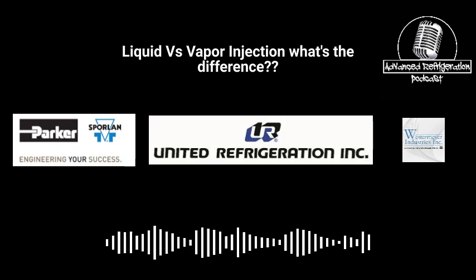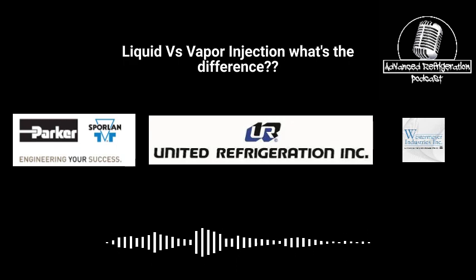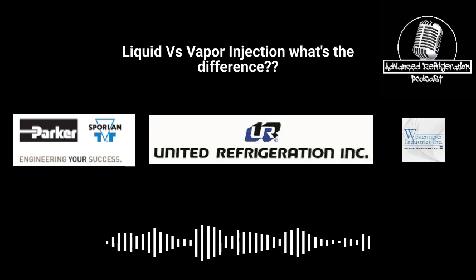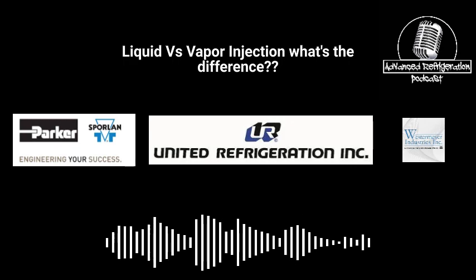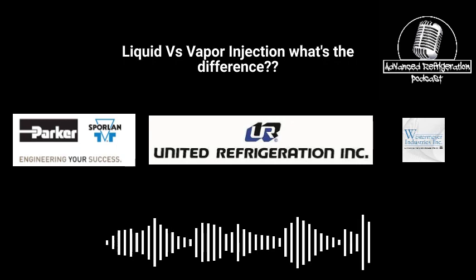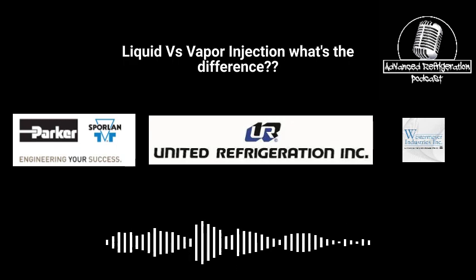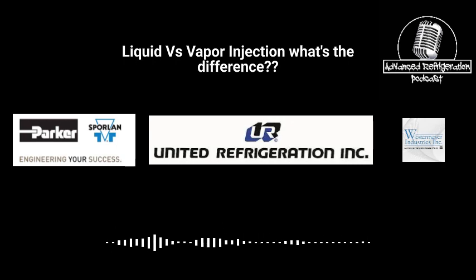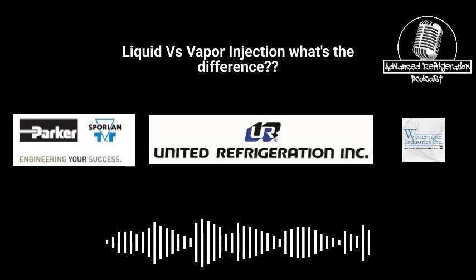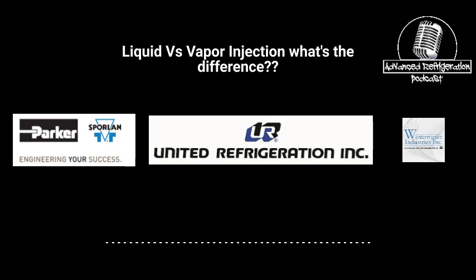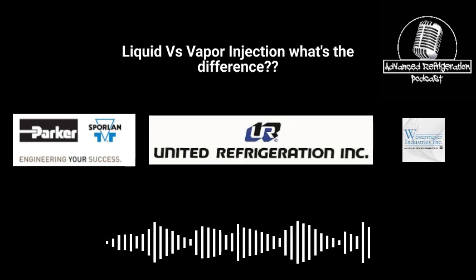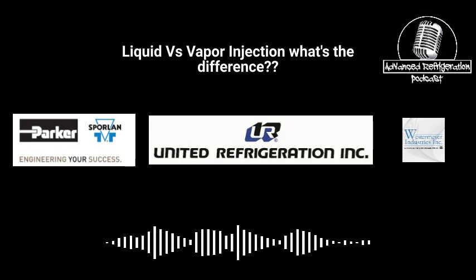Yeah. Go ahead. The other thing you've got to watch out for on vapor injection is flood back. Now this is one that will screw guys up. What I've been doing is putting temp sensors on the vapor lines a lot, so I can graph both. Here's the problem. Guys will show up to a store with one or two compressors off on oil, they'll graph the suction, and they'll see zero flood back. Nothing's coming back in the suction. The suction looks good. But it's coming down the vapor injection line, and it may not be frosting. It may be shoving so much liquid down there that it's not frosting, and it goes right into the crankcase if it's a recip.